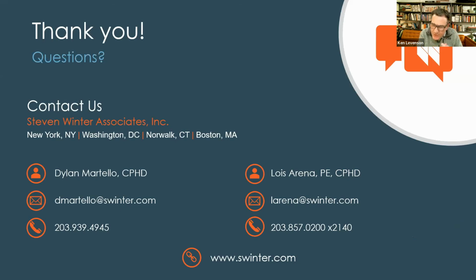One question: how would you design these domestic hot water systems for warm and hot climates like California? The heat pump water heaters are really beneficial in those areas. The package ones you can throw in a garage or a closet in the house and benefit from the cooling side of it, as long as you duct it properly. It's not just that they need airflow to operate - you need to make sure they have proper airflow and aren't ventilated badly from an unconditioned space, which would increase your cooling load. They're used widely out in the Northwest and the West, the air to water heat pumps, so they're pretty familiar there.